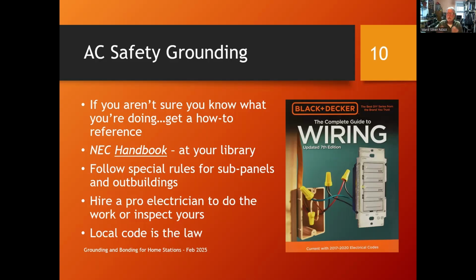People are electrocuted every year because the sub panels are not grounded properly. And so what happens is you create a fairly substantial electrocution risk. Just standing barefoot on concrete, for example, and touching something that's electrified, concrete is way more conductive than you might expect. And people are electrocuted all the time. Follow those rules when you put in a sub panel.